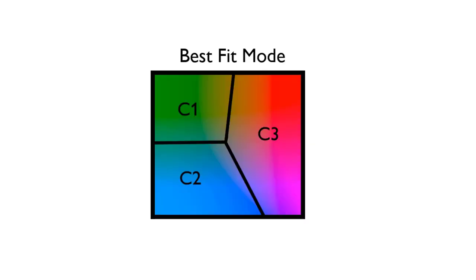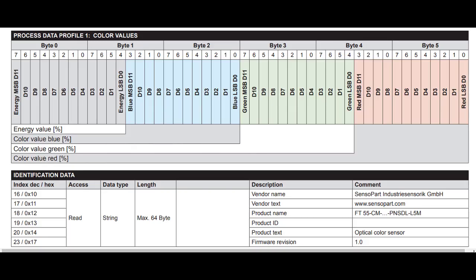When you have really close colors and have to use best fit mode, the sensor will always output one of the taught colors as a found color. And if you have a specification tolerance for a color, obviously that won't work. But you can combine the best of both methods by using the sensor in best fit mode and then sending the data out IO-Link into your PLC.